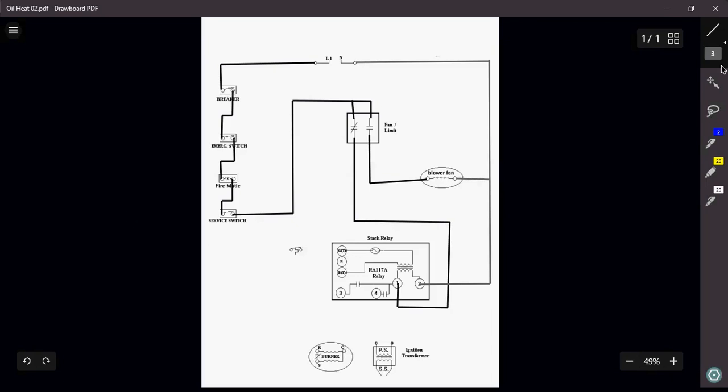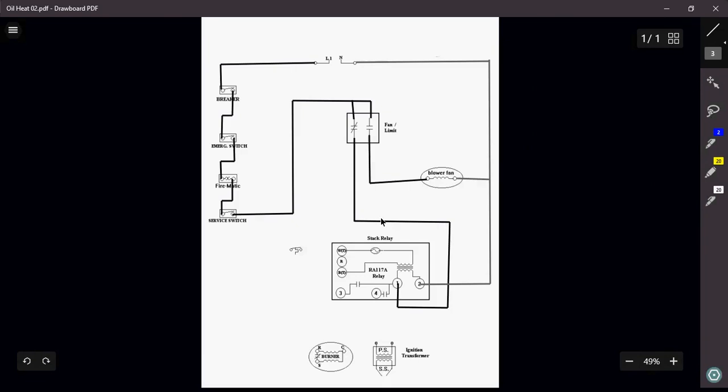Okay, so the rest of this is relatively easy. Now remember, with the stack relay, especially with the RA-117A, terminal 4 and terminal 3 are just simply two separate contacts that are going to close to bring on my burner and my ignition transformer. Terminal 3 is for my burner motor. Terminal 4 is actually for my ignition transformer.